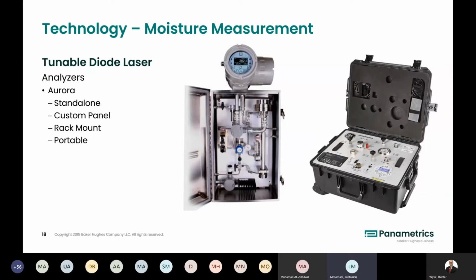So, what's the difference between laser and aluminium oxide? Really, laser is much faster. One of the great challenges of moisture measurement is response time and dry down time, and it's much easier to get a faster response from a laser analyzer than it is from aluminium oxide. Now, moisture, by its nature, is a polar molecule, so it tends to stick to surfaces. So you have to consider all your tubing, all your components. It's not just a pure sensor response time that you have to worry about.